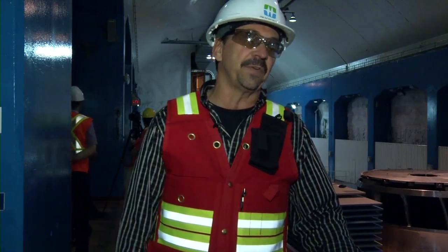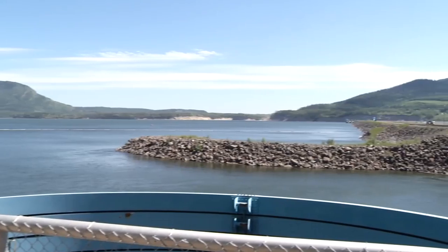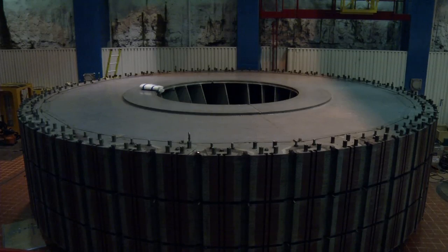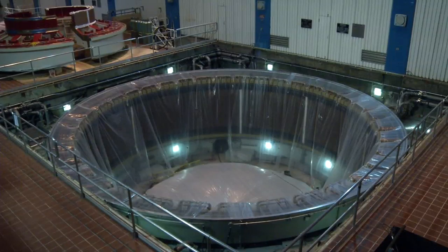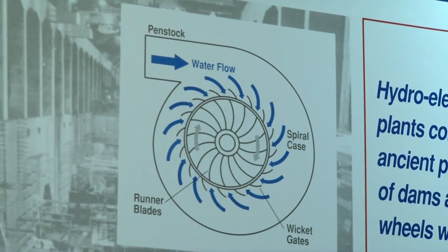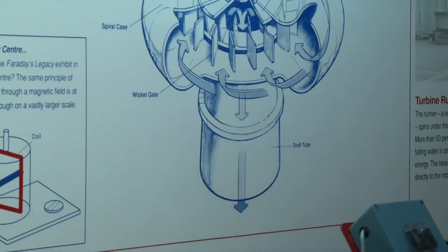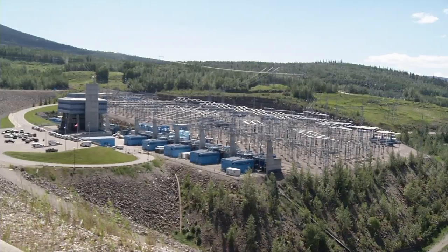We take the energy from the water that's in the lake above, and that water energy is transferred as it moves down into the units through the turbine, which converts the energy in the water to mechanical energy. That mechanical energy is then used to turn the giant rotors that spin within the stator of the generator, generating power at 13.8 kilovolts. That is then sent up through an isophase bus to the wires outside, where it's converted to 500 kilovolts.